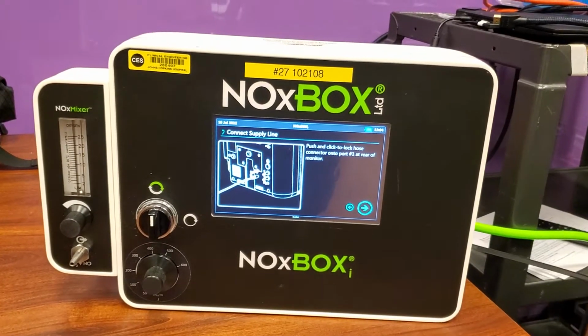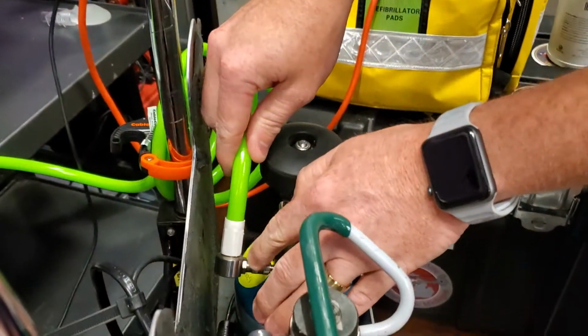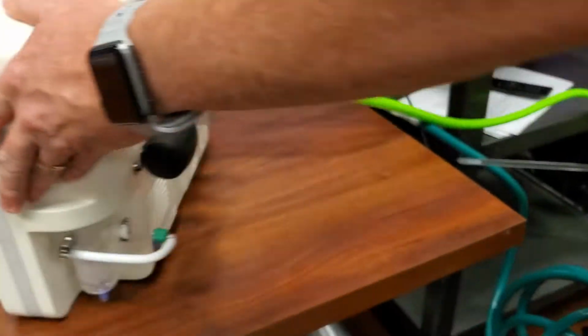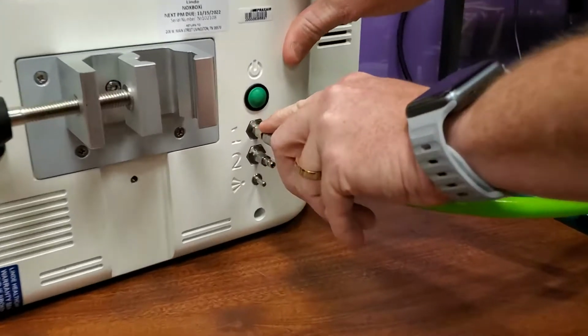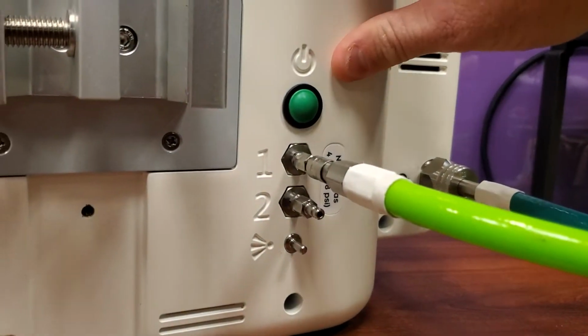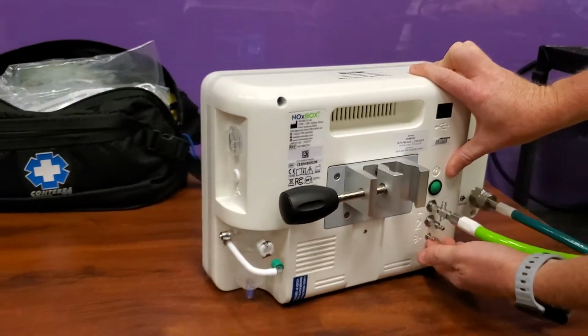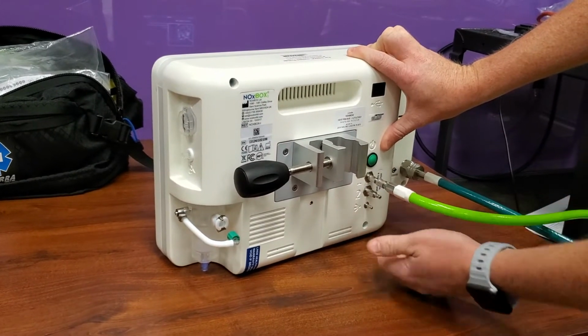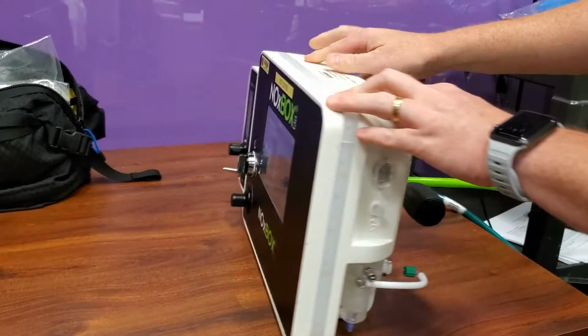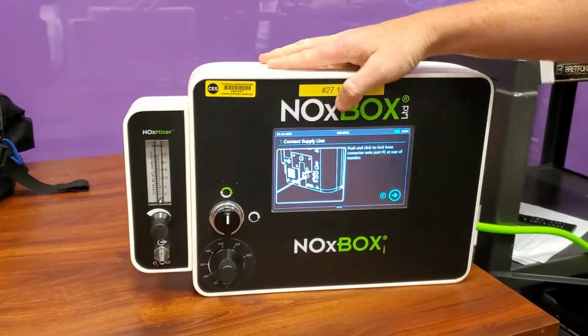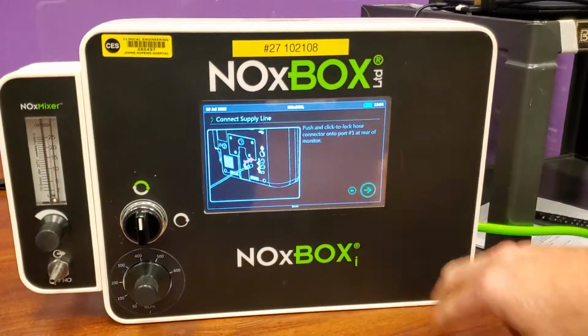Next, we're going to make sure that we're connected in the back here. So we have our piece coming off of the tank here, which is going to be our small right angle here, coming into the back of our NoxBox. And we're always going to be connected to number 1 here. If we did have 2 cylinders, we could go to 1 and 2, and then we just have our purge port at the bottom here, and I'll show you what that's used for as we move forward. So we already have our supply line connected here.